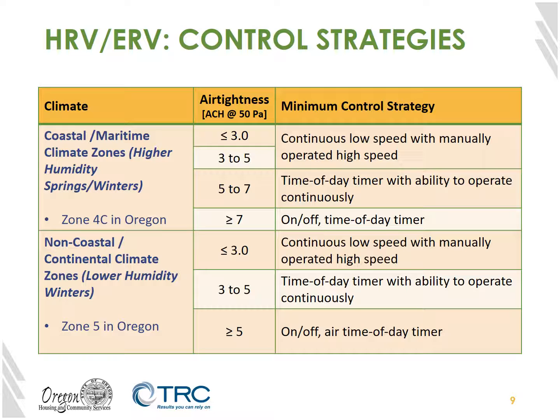we think of continuous low speed with manually operated high speed. Effectively, you set the HRV to continuously move a small amount of air, and there's literally a boost button that a tenant or condo owner can hit to turn the system to a higher speed for the times you really need to move more air. As the building gets a little leakier, you move closer and closer to strictly on-off and time of day timers. The real critical difference here is, again, when you want to make that move. It's different for the marine climate than it would be for the eastern climates. And that's because if we think about it, in eastern Oregon, the winters are much colder for the most part and much hotter in the summer, so we want to have a little bit tighter level of control.